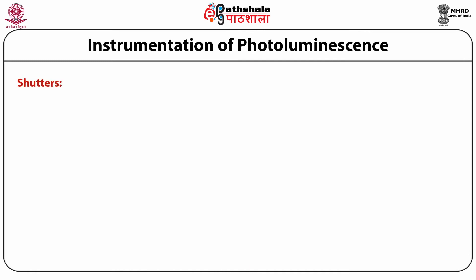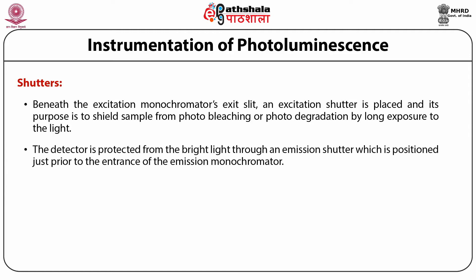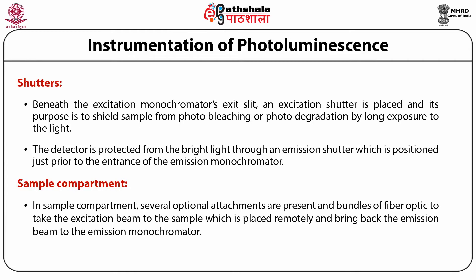Next is the shutter. Beneath the excitation monochromator exit slit, an excitation shutter is placed and its purpose is to shield the sample from photobleaching or photo degradation by long exposure to light. The detector is protected from bright light by an emission shutter positioned just prior to the entrance of the emission monochromator. In the sample compartment, several optional attachments are present, including bundles of fiber optics to take the excitation beam to the remotely placed sample and bring back the emission beam to the emission monochromator.